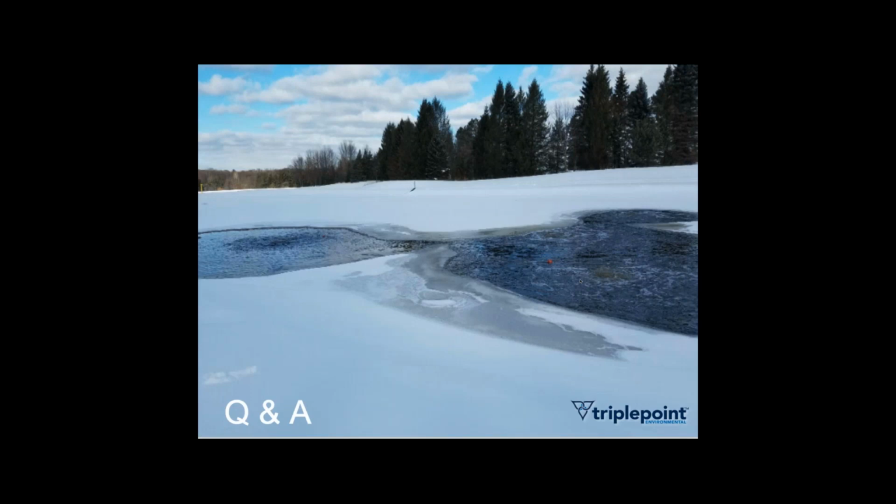Somebody asked the question about the sludge accumulation rate and whether it's based on the area of the lagoon. It is based on the total amount of surface area you have in your lagoon. If you're deeper, for example, then you're going to have relatively less surface area, and you have the potential for those solids to accumulate on the bottom and not get as much access to oxygen, because they're deeper in the water column where there's typically less oxygen without sufficient aeration or mixing. Sludge accumulation rates are based on a lot of things: weather, depth, surface area, etc. All these things come into play.